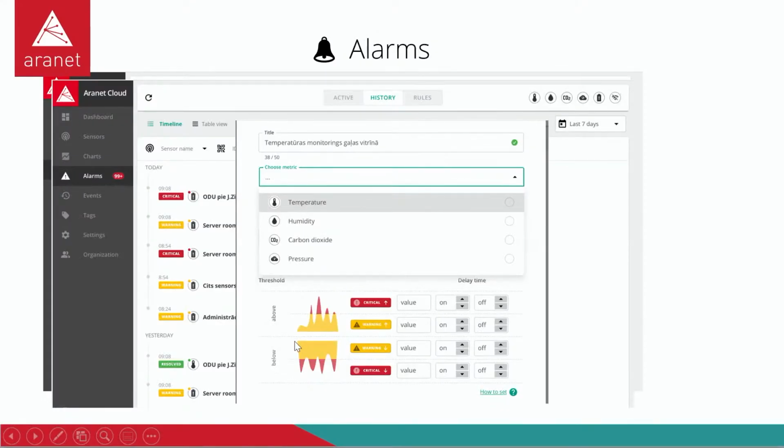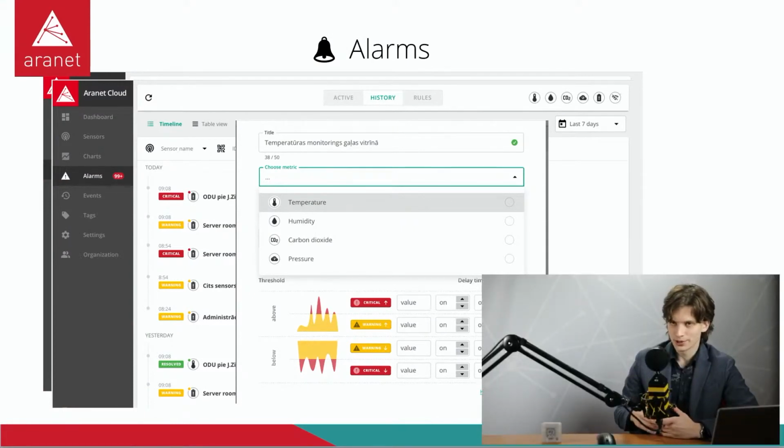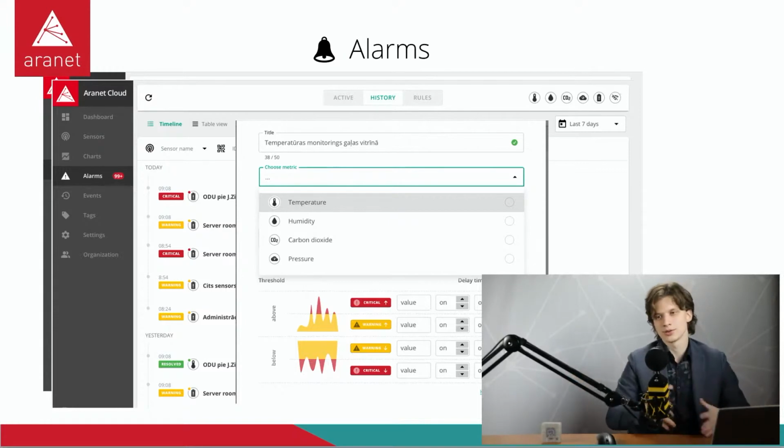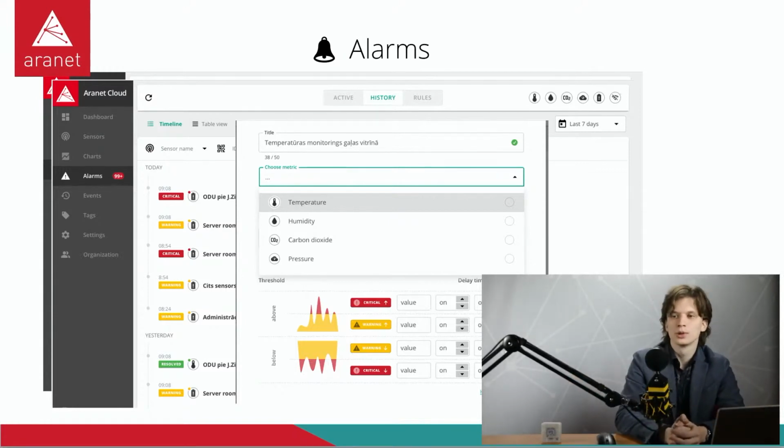So about the alarms and roadmap, how many thresholds will be possible as upper and lower limits with different color severities? 4 levels of alarms, so 2 on the top and 2 on the bottom, as you see here in the presentation. So between, everything is all right, and then there's let's say moderate severity on both the hot and cold side, and then extreme severity also on both the hot and cold side. So as you see here, 4 alarm levels.